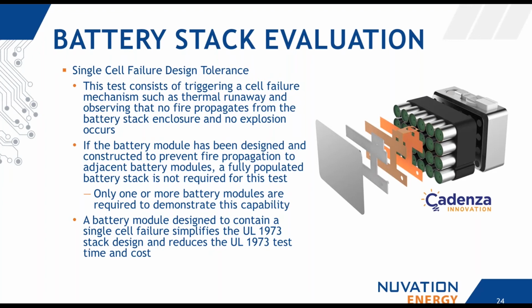And so in an earlier example where that battery stack that uses cells just placed in a metal racking with no thermal separation between cells, the entire battery stack fully populated would have to be evaluated as part of this. So they would actually determine a manner to cause a thermal event in one of those battery cells. And then they would do that with a fully populated stack and see how it propagates.